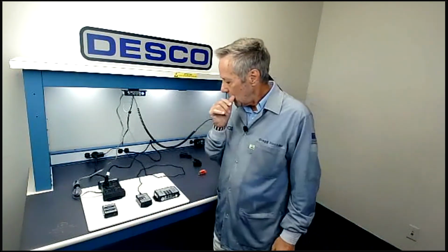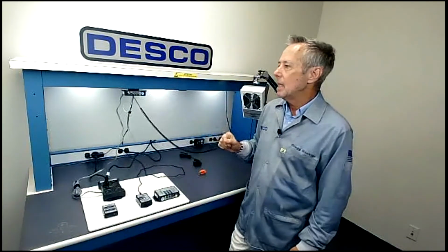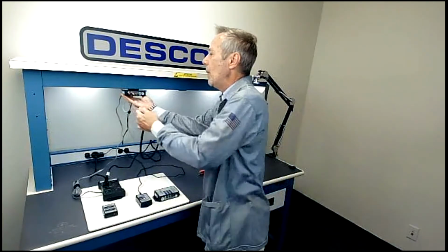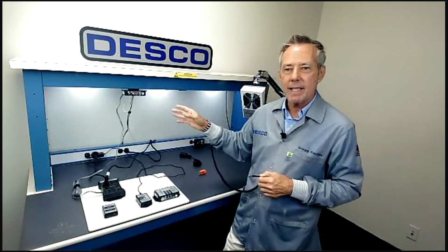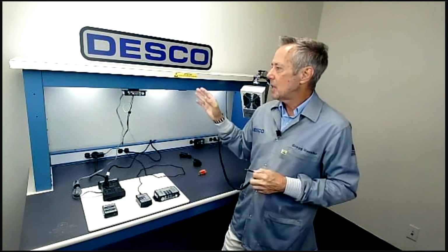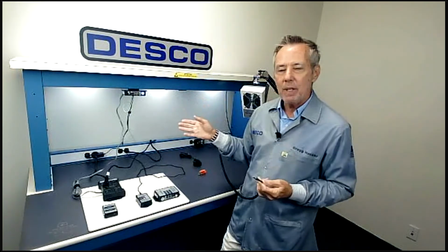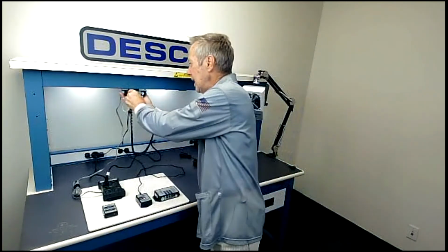That's a very good question. These monitors also have a feature where, let's say I get up, walk away, or roll my chair over, stretch that out, and yank my banana plug out. If I do that without parking it, I'm going to get an alarm, and that alarm will last for 8 seconds and then stop. This is another great warning feature that something has happened that wasn't supposed to. That's a legitimate fault. When I plug back in, I'm ready to go again.